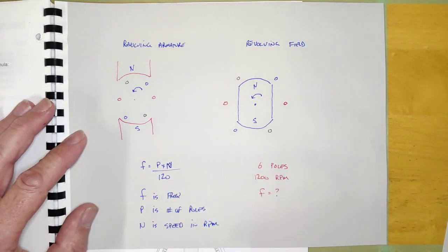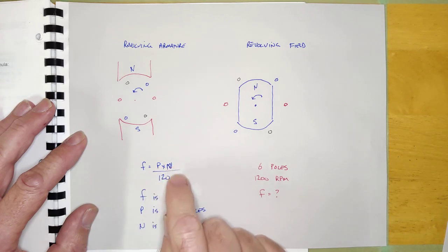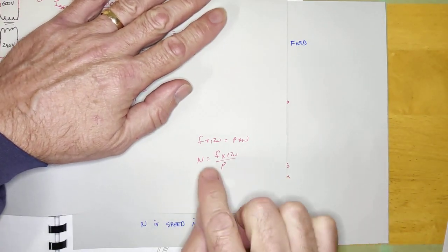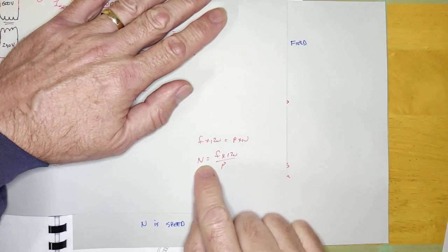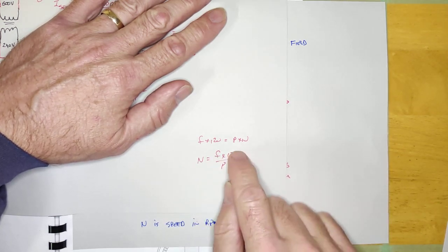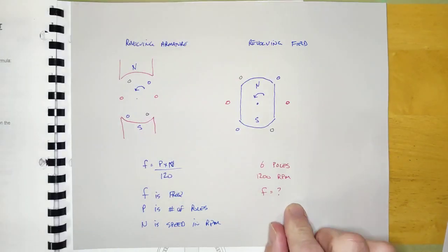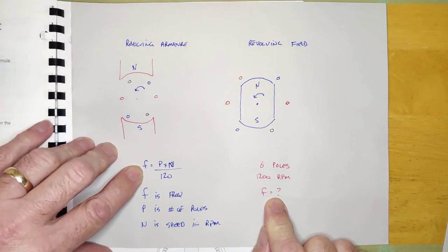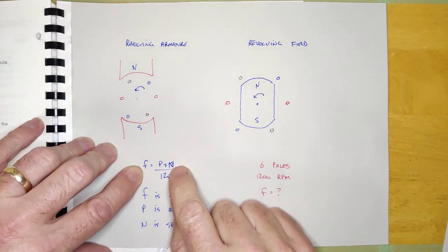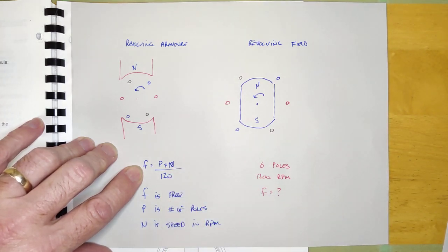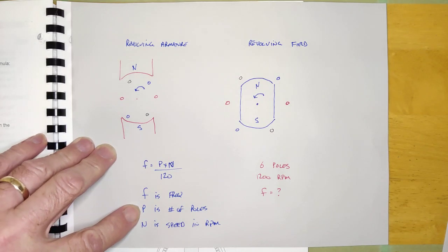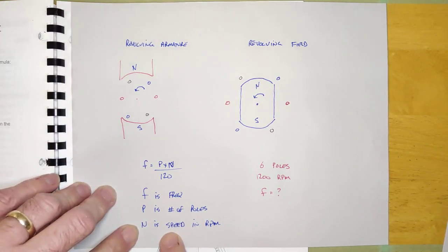The other thing I want to talk to you about is this formula: F equals P times N over 120. You've been using a very similar formula in electronics for figuring out the sync speed of a motor. This same formula, transformed differently, calculates the frequency that a generator outputs if I know the number of poles it has and how fast it's turning. F is the output frequency, P is the number of poles, N is the speed in RPM, and 120 is a constant.